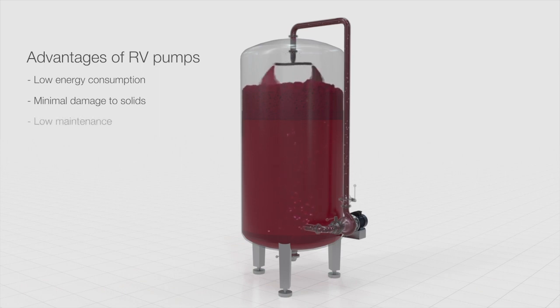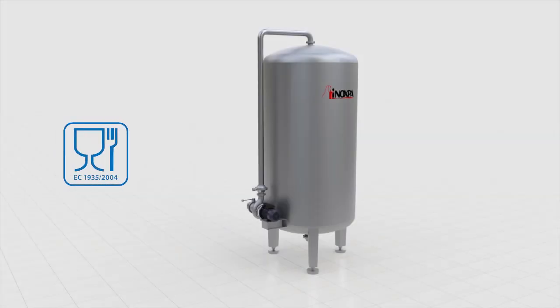Low maintenance thanks to the small number of components. Unlike other pump technologies, RV pump can handle must with solid particles without clogging, so there is no need to place a grid to serve as a strainer in the tank. The O-rings and mechanical seals installed on RV pumps are food grade, so they fulfill the regulation EC 1935-2004, mandatory in Europe, and also the FDA. To obtain high quality wines, it is important to use highly efficient pumps.